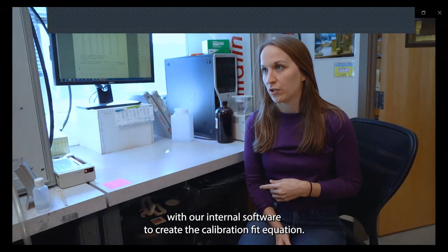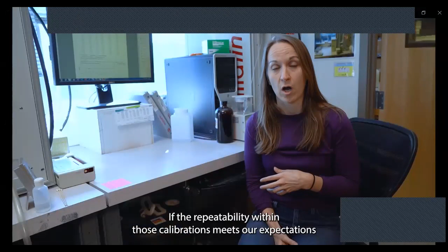So after our sensors go through calibration, we analyze the data with our internal software to create the calibration fit equation. And at that point, then we can review whether the calibration residuals fall within the expected range. And if that's good, then it'll typically go on to the second calibration. And then if the repeatability within those calibrations meets our expectation for the sensor, then we consider it to be a good sensor.